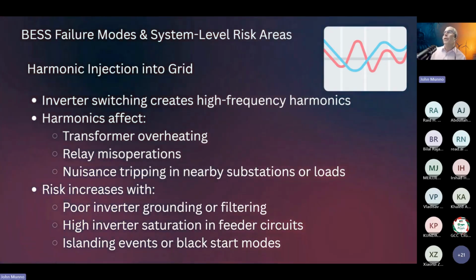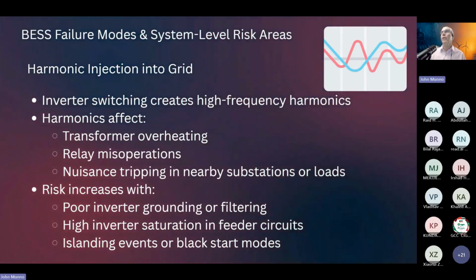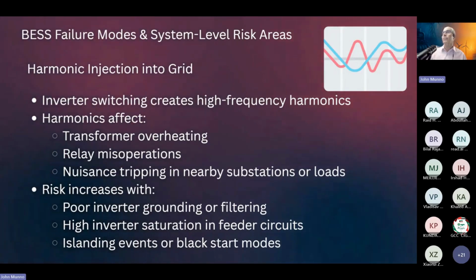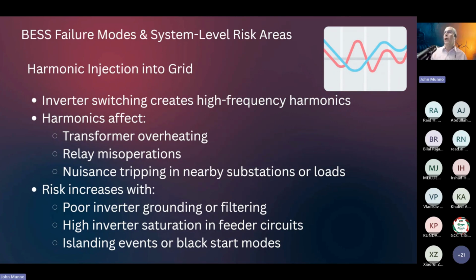What else? This is when we get into a little bit of the impact on the grid: harmonic injection into the grid. Inverter switching creates high frequency harmonics. What that'll do out on the grid is overload or overheat transformers. It can cause misoperation of relays. It can cause nuisance tripping in nearby substations or loads. And this risk increases if you have poor inverter grounding or filtering, or high inverter saturation in feeder circuits.